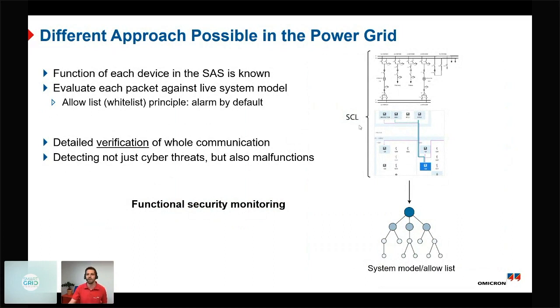This SCL file can also be used by the intrusion detection system to create a system model, an allow list, formerly called whitelist, of all the communication, and then compare each and every packet against this allow list. If you do this in more detail in a digital substation with the 61850 traffic, you can perform a detailed verification of the behavior of the communication.